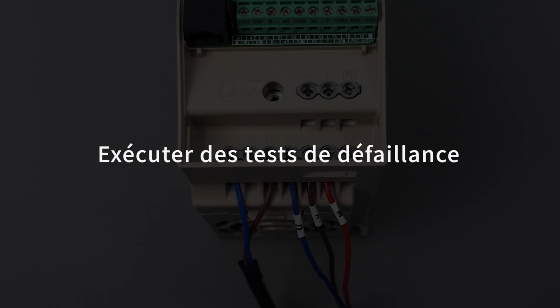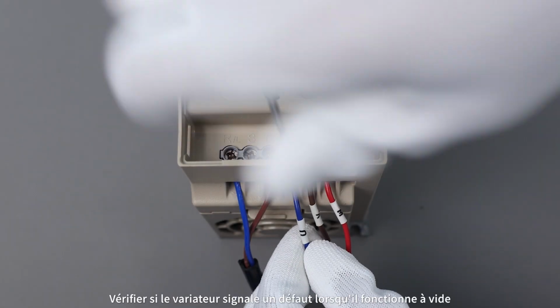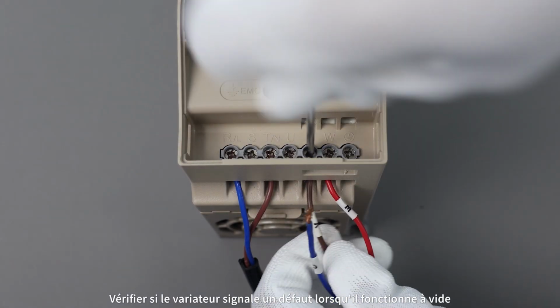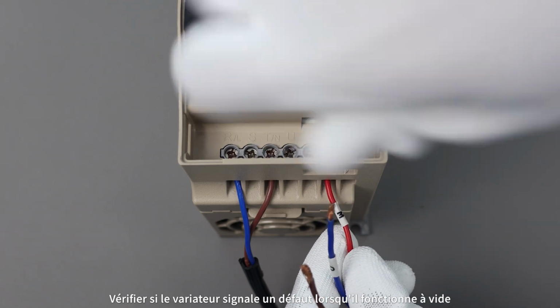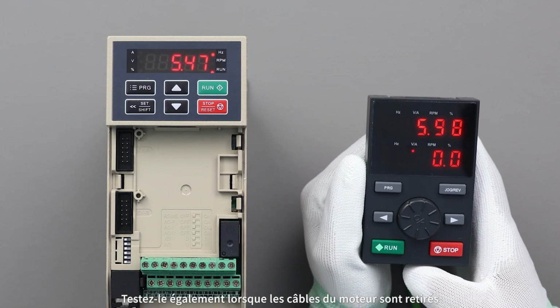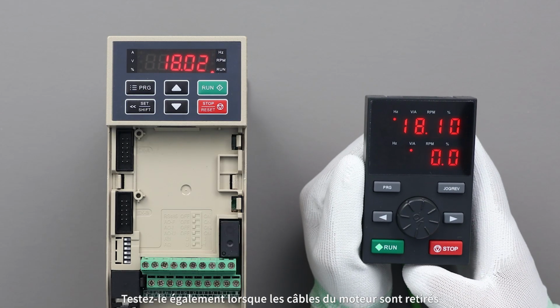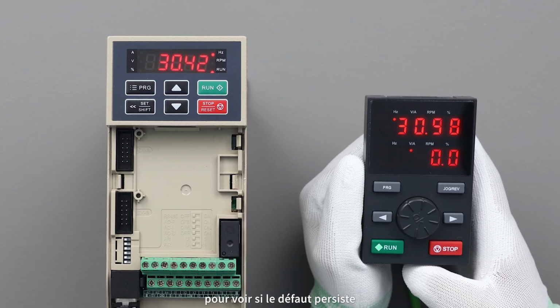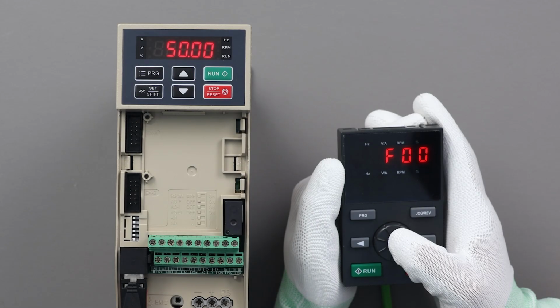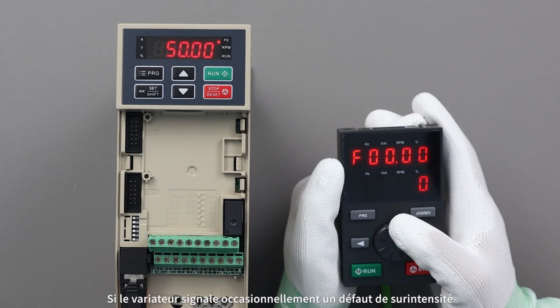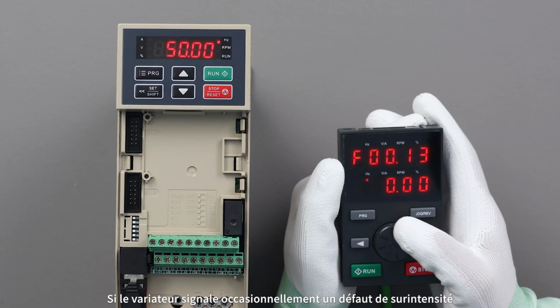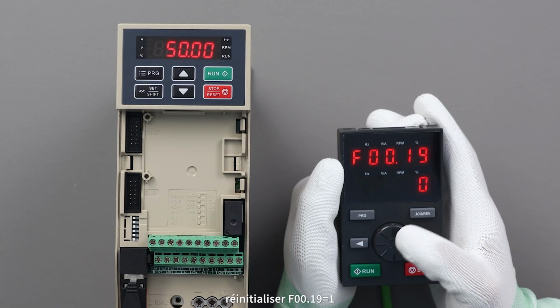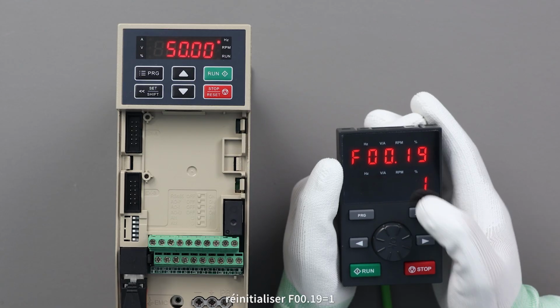Run fault test. Check if the inverter reports a fault when running without a load. Also, test it with the motor cables removed to see if the fault still occurs. Analyze the overcurrent fault. If the inverter occasionally reports an overcurrent fault, reset it F00.19 to set 1.